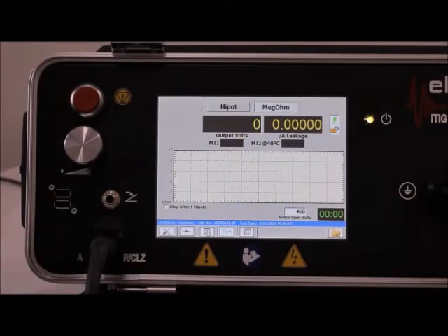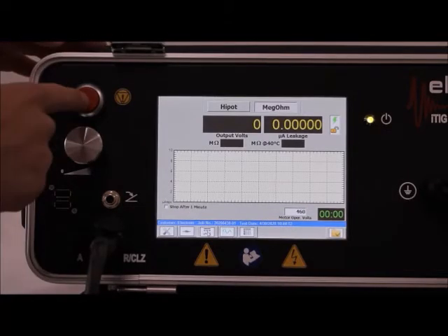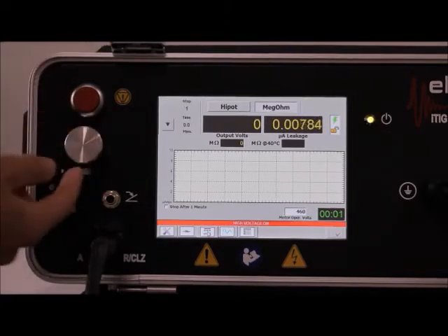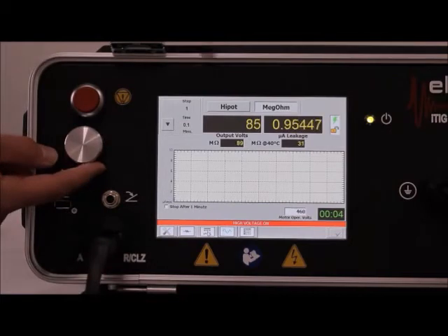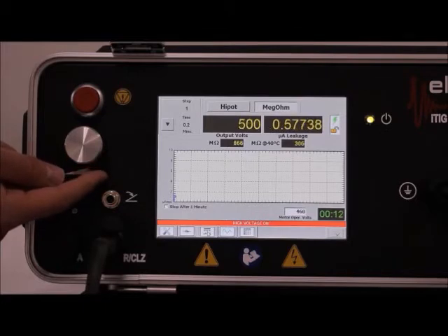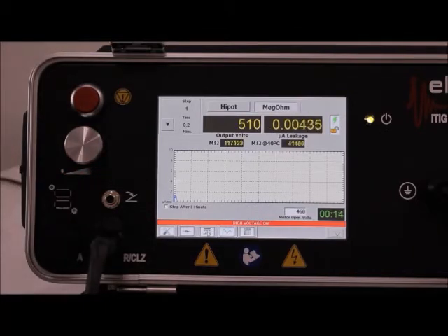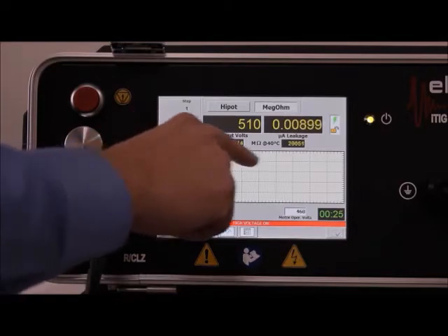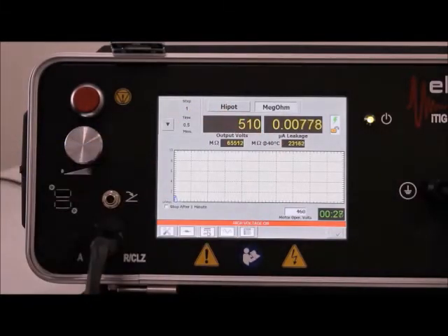Commonly tested on low voltage motors for the megohm measurement is 500 volts. Press the red button. Use the silver dial to turn the voltage up. So you can see the applied voltage near the top center. As I'm turning the voltage higher, or increasing the voltage, you can see the inrush current. So stop turning the voltage up, it will drop off. And as we wait here, it will stabilize. We calculate the megohm measurement here and correct it to 40 degrees Celsius.